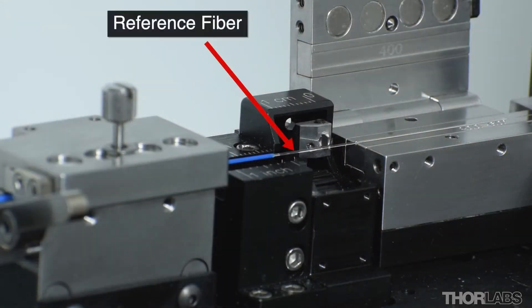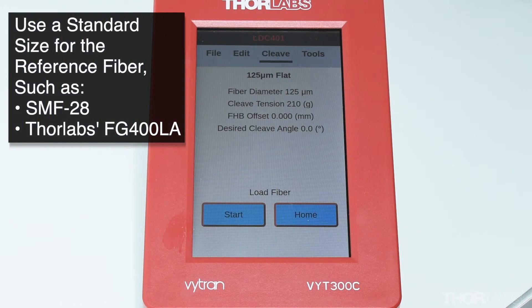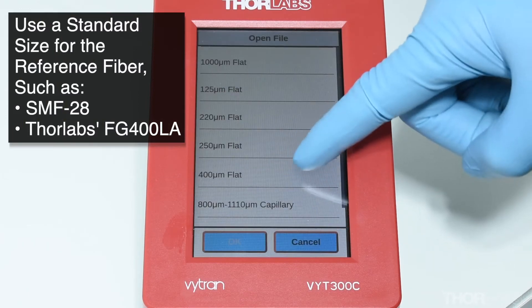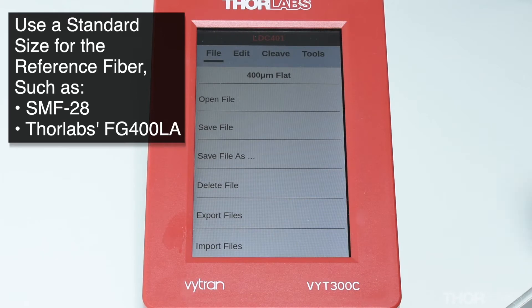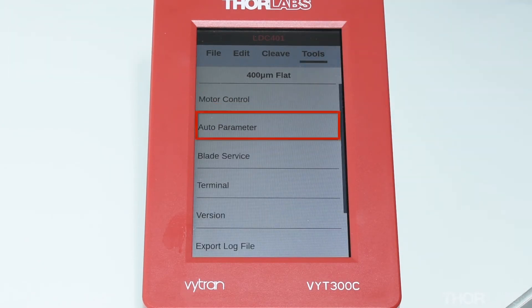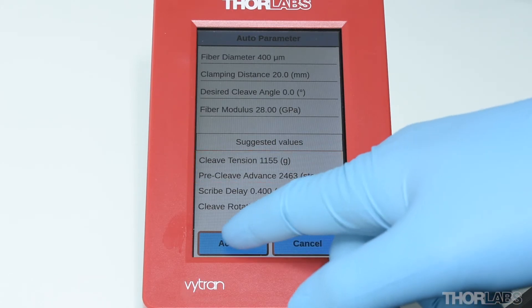When verifying the blade offset, it is helpful to use a piece of fiber as a reference. Use the handset controller to either load or set up a cleave file for a standard fiber size which matches your reference fiber. For example, SMF28 or Thorlabs FG400LA can be used. If the original factory file has been modified, the auto-parameter tool on the handset can be used to ensure that the correct cleave tension and pre-cleave advance are set for the reference fiber's diameter.